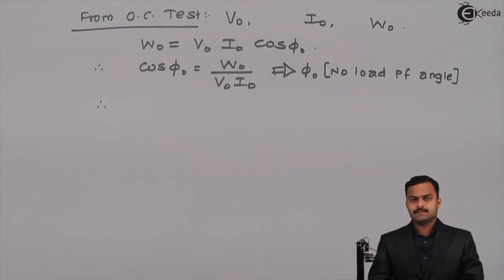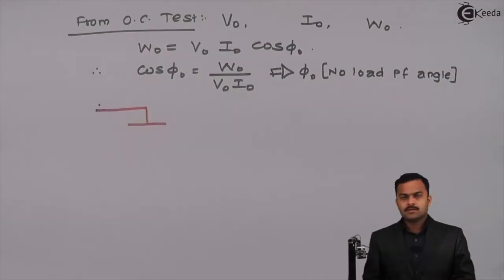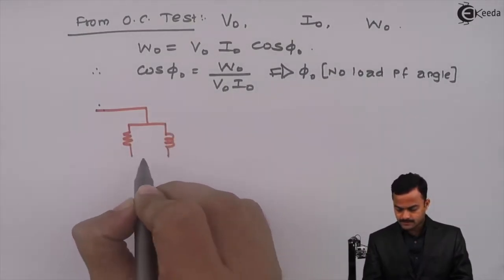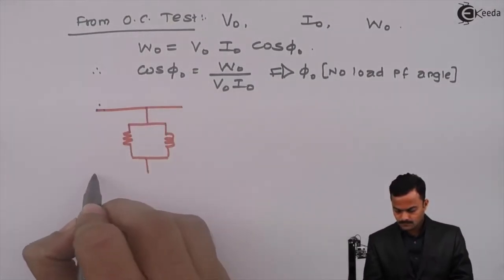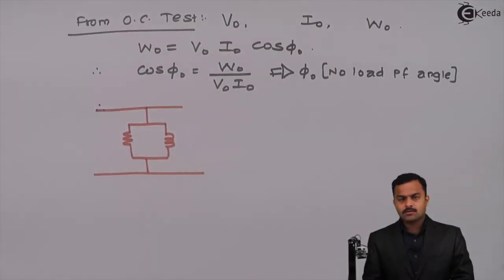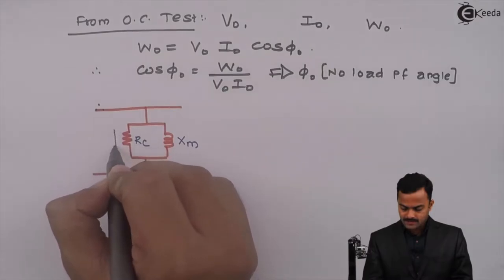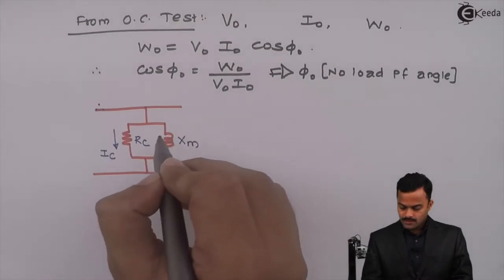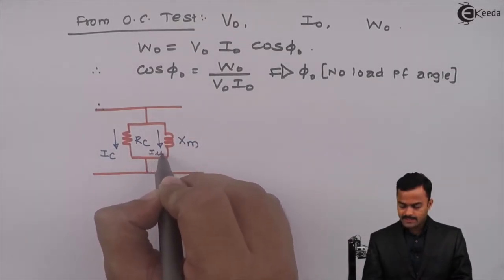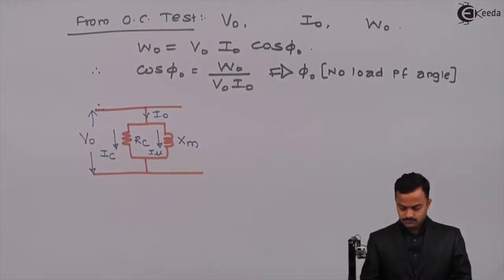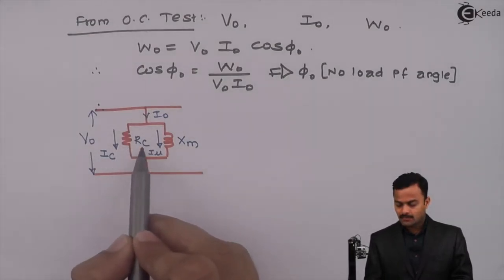I will explain this with a simple circuit and a phasor diagram. In the circuit we have a parallel combination of a resistance and an inductance. The resistance is called the core loss resistance RC, and the inductance has a magnetizing reactance Xm. The current through RC is the core loss component of I0, and the current through Xm is Iμ, the magnetizing component of I0. The no-load voltage V0 is applied across them. The objective of the OC test is to get the values of RC and Xm.